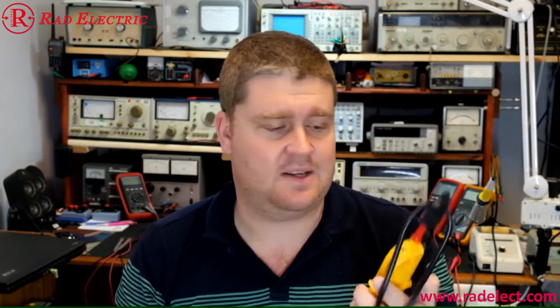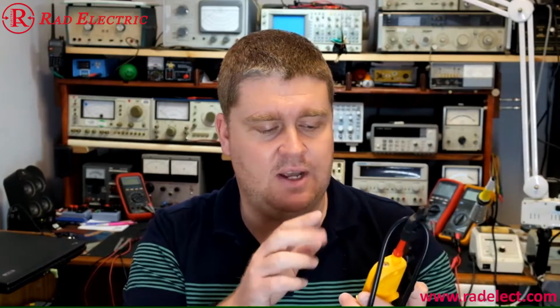It's not meant to replace a dedicated multimeter or digital multimeter of any standard, but it does give you an indication of DC and AC volts from 12 to 690. I've tested it down to 9, but it cannot give you an indication of 9, it just shows you 12.